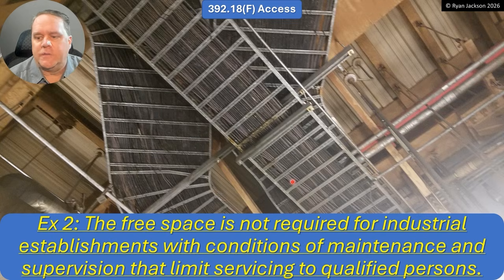Exception 2. Free space is not required for industrial establishments with conditions of maintenance and supervision that limit servicing to qualified persons. So I think this is a complete total get out of jail free card if you're in a supervised industrial location. So I don't think that any free space whatsoever is required. I think that's the intent, and that's the way I would enforce it.